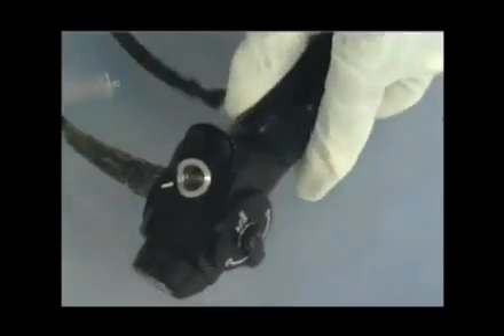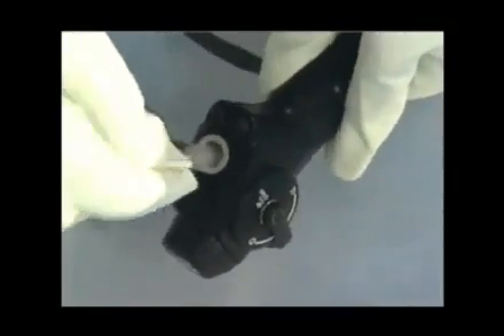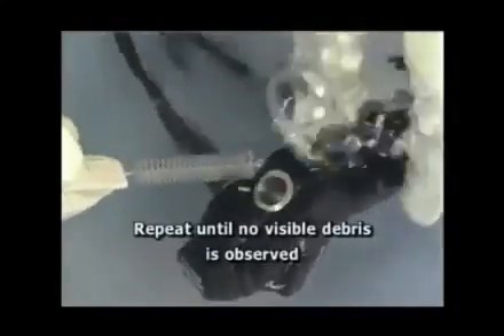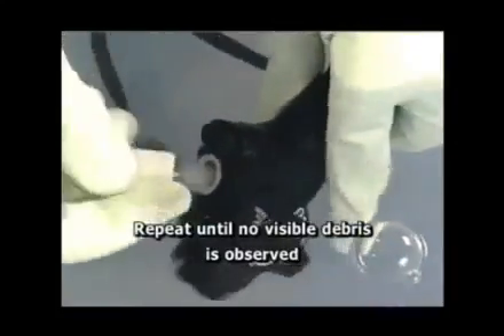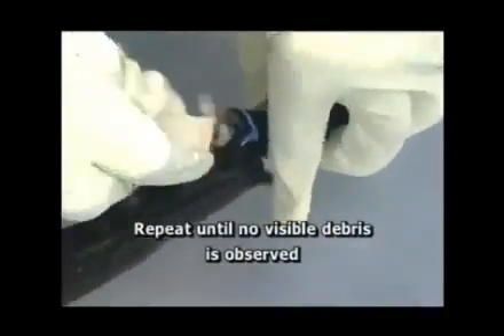The next step is to clean the channel openings. Carefully insert about 1/2 of the channel opening brush into the suction valve housing. Rotate the brush and remove. Clean the bristles. Repeat this procedure until no visible debris remains. Now move down to the instrument channel port. Insert the brush. Rotate and remove. Clean the bristles, and repeat until no visible debris remains.